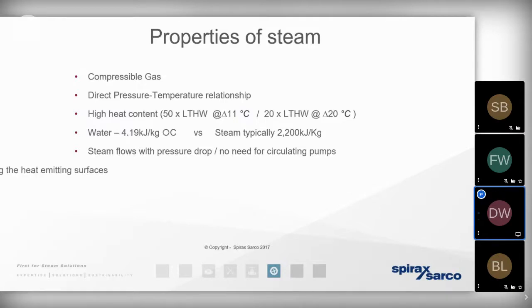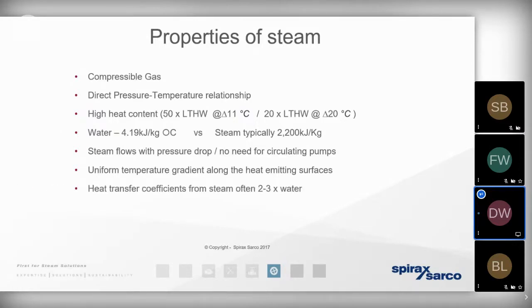We also know that steam, as a gas, it gives up its heat energy equally and evenly across the entirety of the heat transfer surface area. So you remember from the presentation we went through 2 weeks ago when we looked at the uses of steam for heat exchange applications, we've mentioned that that equal and efficient use of the heat transfer surface area is just one of the reasons why we need a smaller heat exchanger when we're using steam compared to using water. We also know that because steam gives up its heat energy by condensing, the speed of heat transfer is approximately 3 times greater than with a water-to-water heat exchanger.